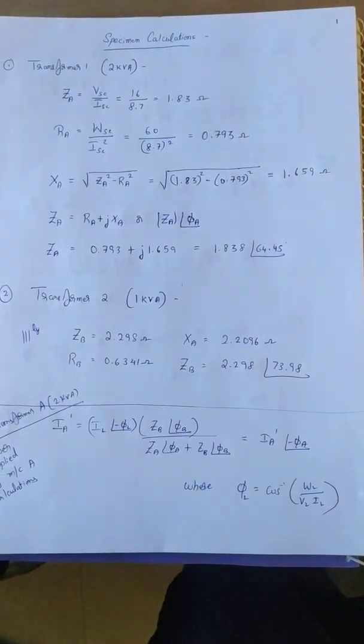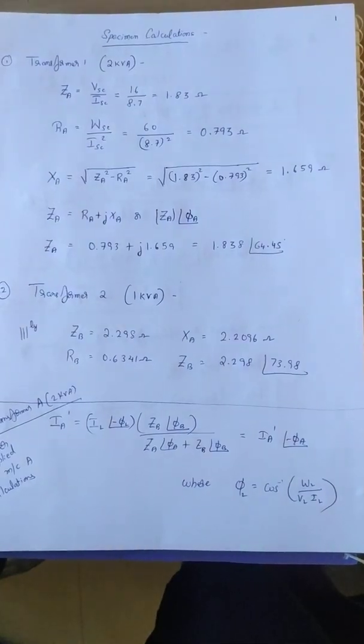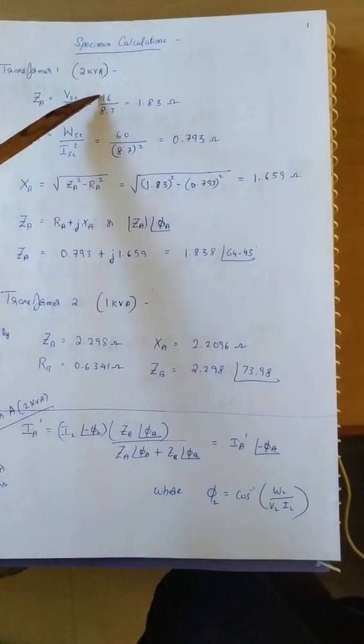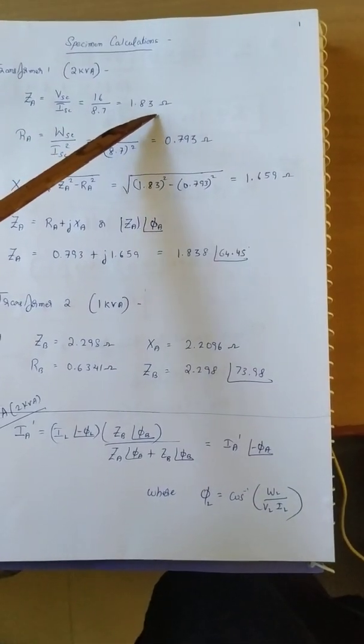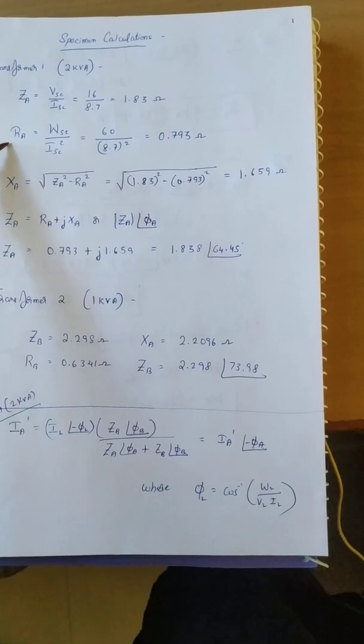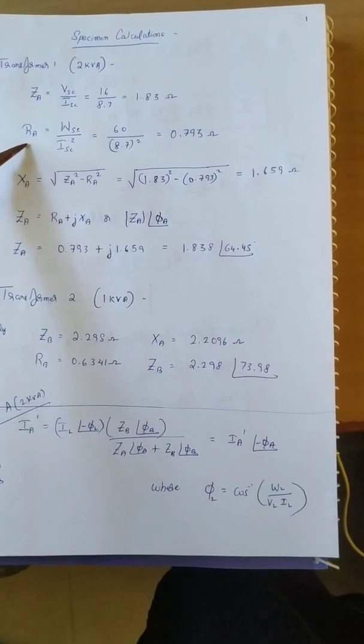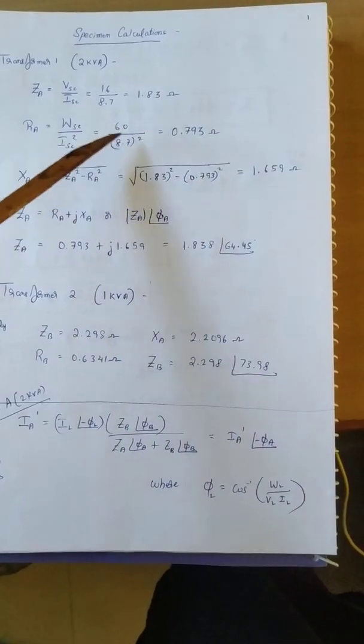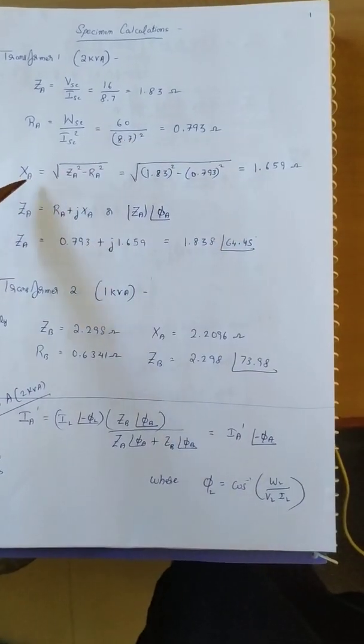First we calculate ZA which is obtained by VSC divided by ISC. As per the reading that we have got, VSC is 16, ISC is 8.7. If we take the ratio we will be getting 1.83 ohms. Then we will be calculating resistance RA. If we call this as Transformer A, WSC divided by ISC square which will get 60 by 8.7 square which is 0.793 ohms.